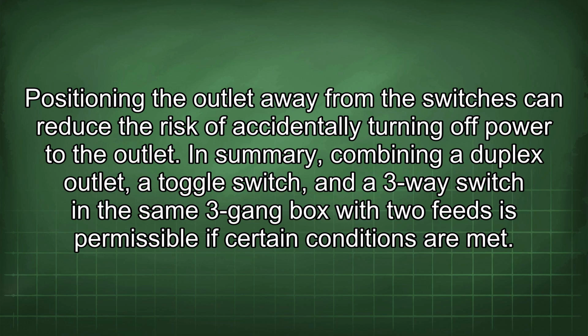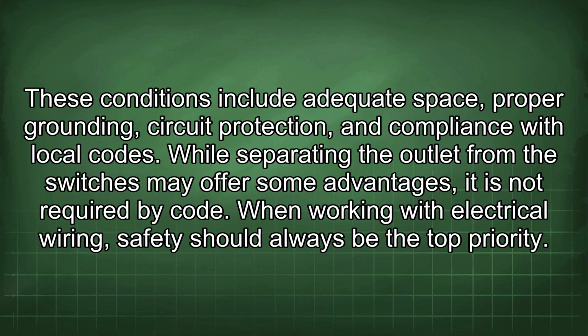In summary, combining a duplex outlet, a toggle switch, and a three-way switch in the same three-gang box with two feeds is permissible if certain conditions are met. These conditions include adequate space, proper grounding, circuit protection, and compliance with local codes. While separating the outlet from the switches may offer some advantages, it is not required by code. When working with electrical wiring, safety should always be the top priority.